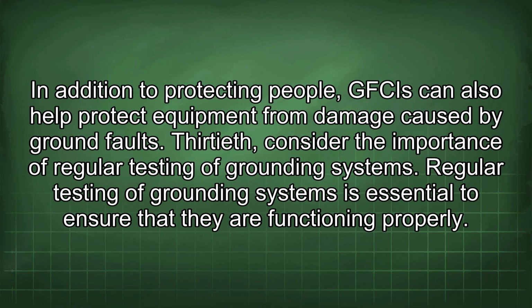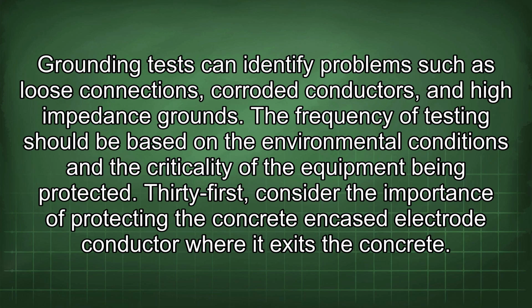30th, consider the importance of regular testing of grounding systems. Regular testing of grounding systems is essential to ensure that they are functioning properly. Grounding tests can identify problems such as loose connections, corroded conductors, and high impedance grounds. The frequency of testing should be based on the environmental conditions and the criticality of the equipment being protected.